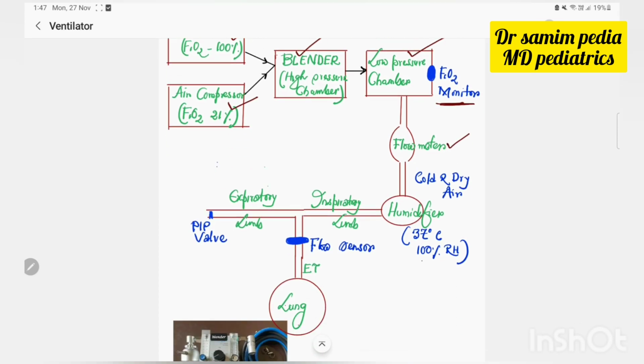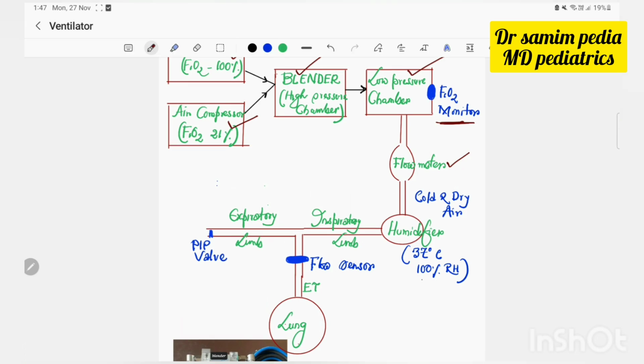Air that comes from the flow meter is cold and dry, which can damage the airway. So this cold and dry oxygen should go through a humidifier, which humidifies the oxygen to 100% relative humidity and warms the oxygen to 37 degrees Celsius. Then oxygen goes to the inspiratory limb and from the inspiratory limb to the expiratory limb. But intermittently oxygen goes to the lung via the endotracheal tube.